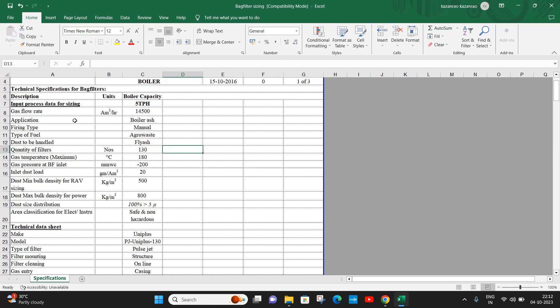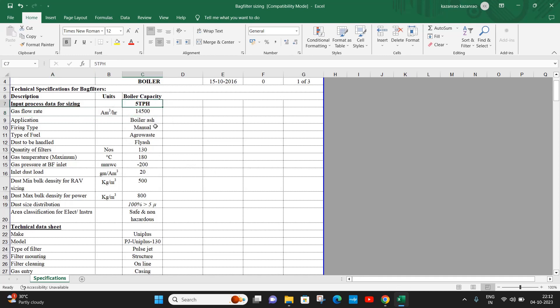Now let us see the sizing of bag filter using air to cloth ratio. This is a typical specification for a 5 TPH agro waste fired boiler. The gas volume is 14,500 actual meter cube per hour.